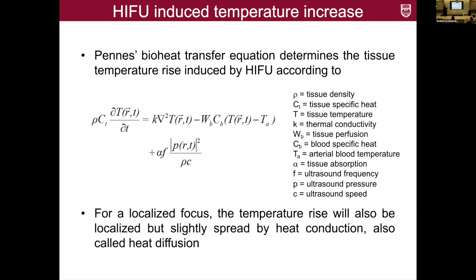There is an equation that determines the temperature rise that is introduced by HIFU. For the localized focus, the temperature rise will also be slightly spread by heat conduction and heat diffusion. You can see there are many tissue parameters that contribute: the tissue temperature, the perfusion, the absorption, and so on. So different tissues will behave differently to the ultrasound beam. What we try to achieve is a thermal necrosis, here shown in red. We have to elevate the temperature to a certain level to reach the coagulation limit. Normally the protein denaturation is around 56 degrees Celsius, but you can also achieve it by applying longer pulses to heat the tissue up.